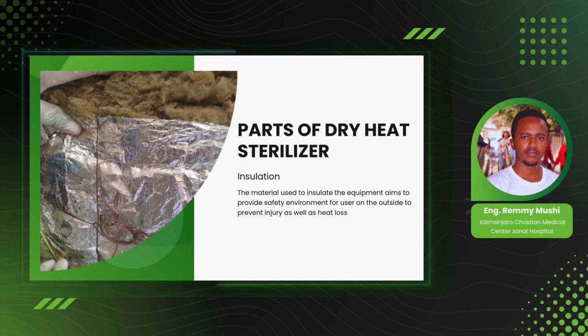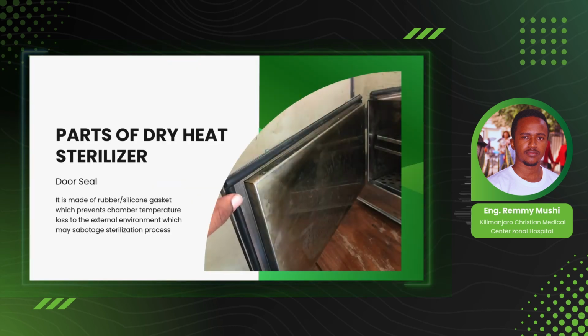In most cases, the insulation used is glass wool, which is very good at insulating the chamber. The chamber is usually surrounded by glass wool to ensure there is no heat loss towards the machine or the door that could injure the user. Then there is the door seal, the fifth part. As we can see in the picture, where the hand is, there is something like rubber. It prevents heat loss from inside the chamber to the surroundings of the machine. This door seal can be made of rubber or silicone.